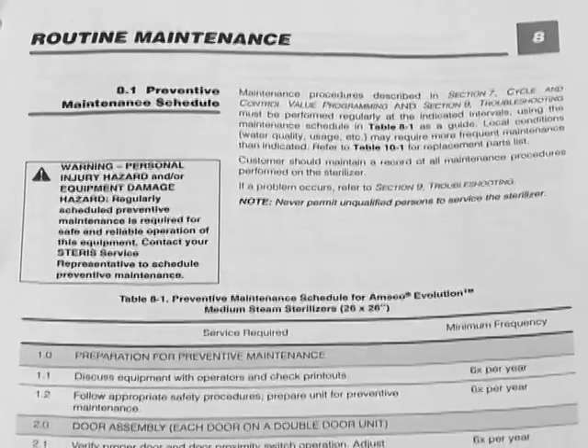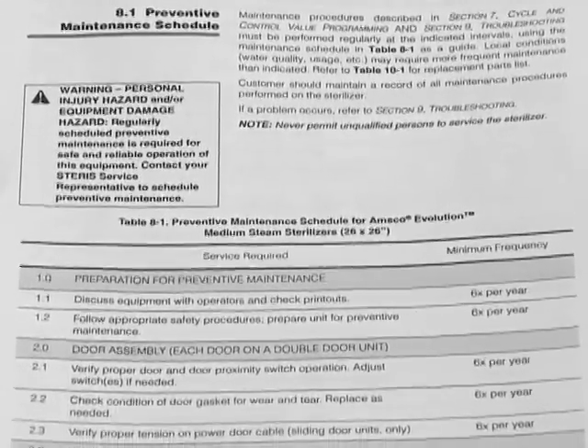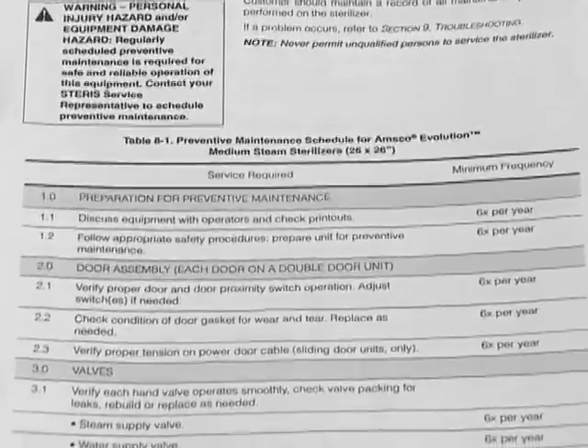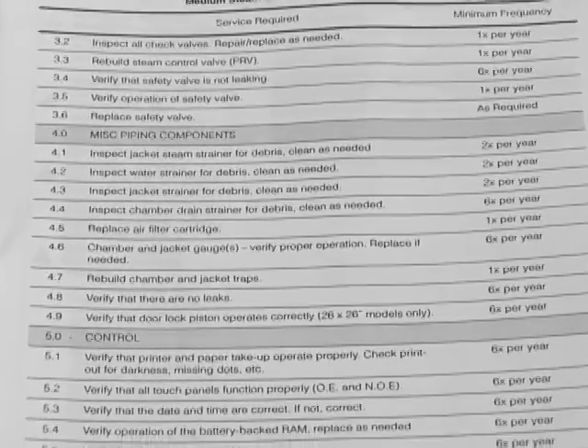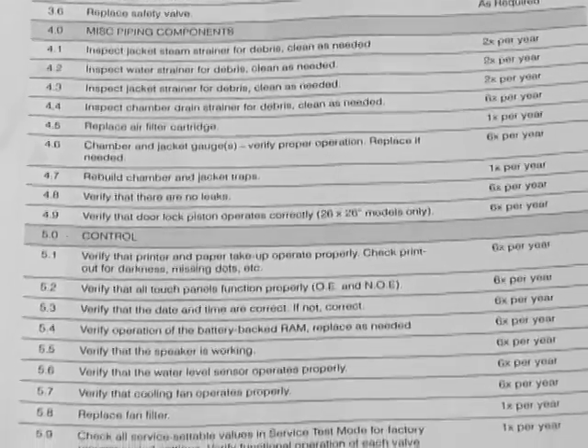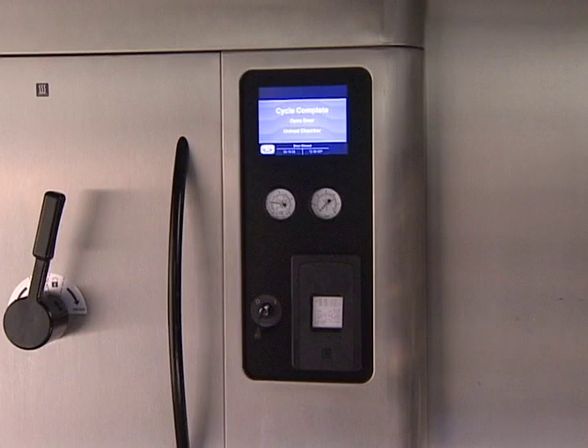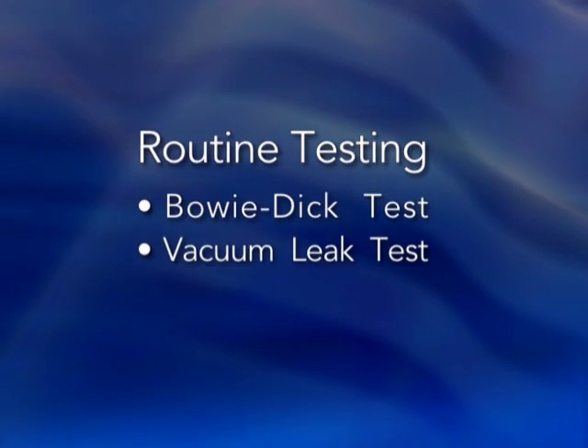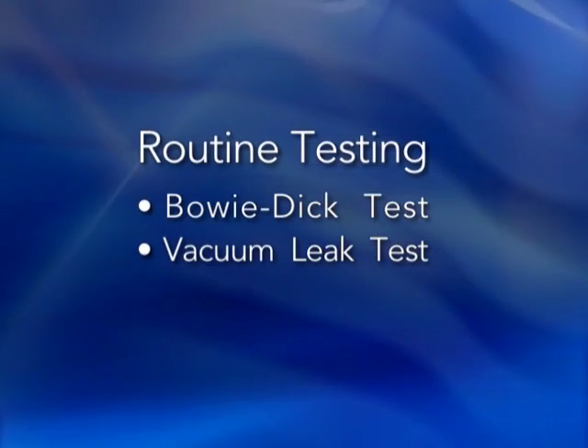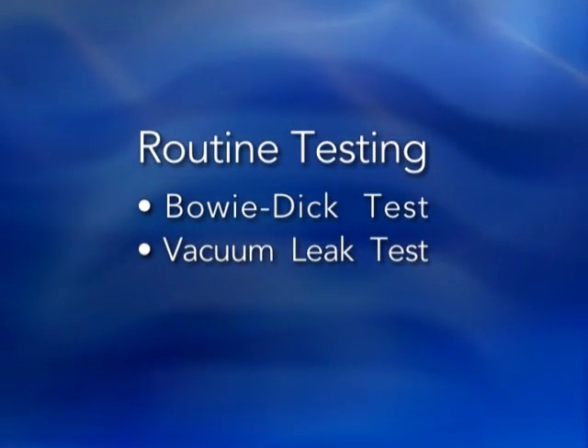A complete maintenance schedule can be found in Section 8 of your Evolution Operator Manual. Where indicated, some maintenance activities should be performed by a qualified service technician. Remember to let the sterilizer cool down before you perform any maintenance. For sterilizer monitoring, you'll run a Bowie-Dick or DART test and a vacuum leak test.